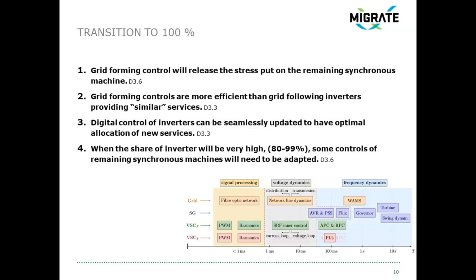Another interesting part is that, being digitally controlled, inverters can be updated remotely, and you can also adapt the ancillary services, the gains and the inertia you provide depending on the generation mix, even if it changes within days. One interesting point also is that when you reach very high penetration of inverters, you might need to retune some of the machine controls, especially the PSS control. PSS were designed for a system with only synchronous machines and, I would say, slower oscillations. If you go to a system with only inverters or almost only inverters, the oscillations of the system would change, and therefore it's quite obvious that you need to retune the power system stabilizers.